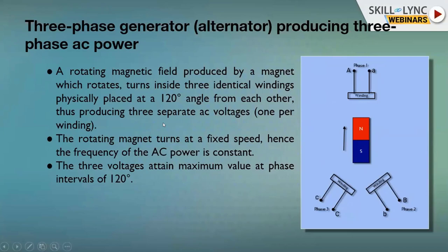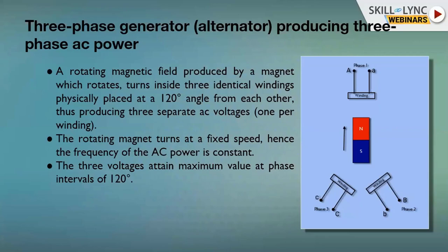A rotating magnetic field is produced by a magnet that rotates inside three identical windings physically displaced at 120 degrees from each other, producing three separate AC voltages — one in each winding. The R phase develops one voltage; the Y phase develops a voltage lagging by 120 degrees; the B phase develops a voltage lagging by 240 degrees. The generators used at generating stations are called synchronous generators, rotating at a fixed speed.